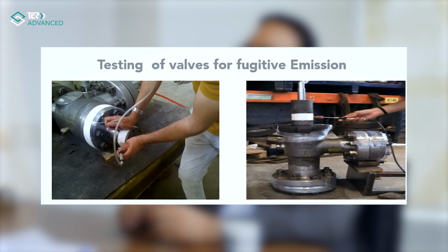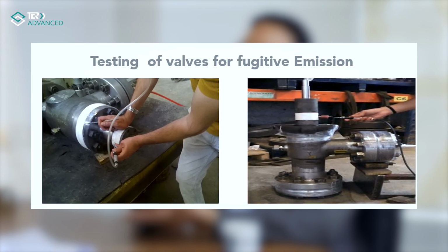In valves, there is a movable mechanical shaft and a stationary pressure-containing valve body. Due to wear and tear, there is a chance of leakage from the shaft in a valve. That is a major concern. When the valve is handling corrosive or lethal fluids, it is very much required to identify whether there is any leakage, which is generally called the fugitive emission technique, where there are chances of very trace-level fluid or gas escaping from the shaft joints.